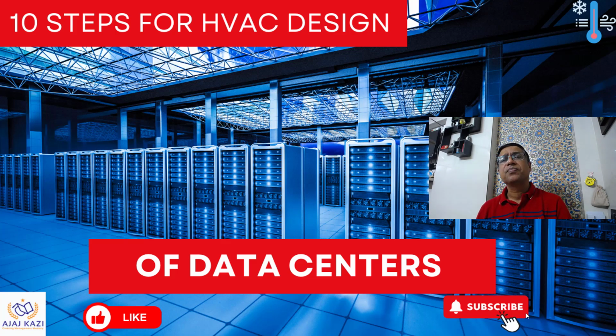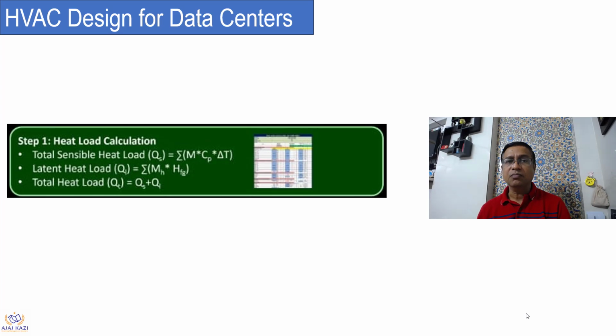What are the 10 steps for HVAC design for efficient data center operation is what we are going to look at in this video. There could be more steps, but let us look at 10 steps. One of the important aspects in a data center is heat load calculation. In a data center, the major source is sensible heat. The latent heat is less, but if it is there, we need to calculate, and we should be very clear about total heat load, sensible plus latent.